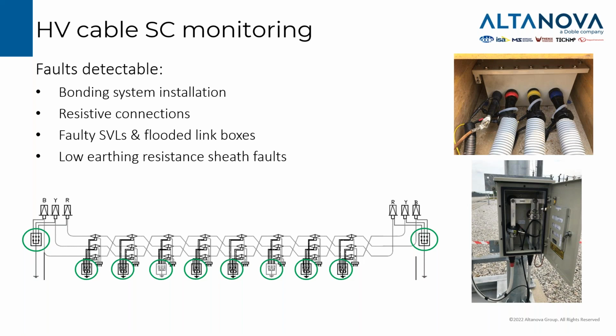Last, there is also the sheath current monitoring, so we can study the behavior of the grounding and the sheath connections in the cable. We can prevent wrong bonding system installation, resistive connection in the link boxes or in the termination boxes, faulty surge voltage limiters or flooded link boxes, and sheath faults where there is a low earthing resistance.